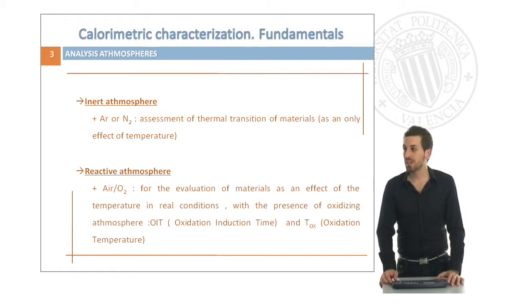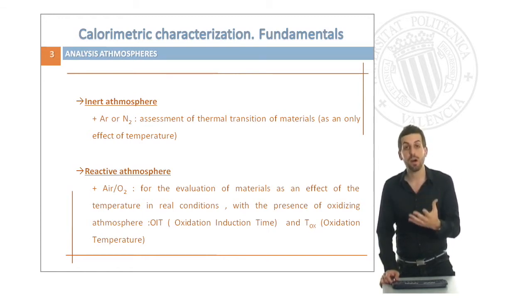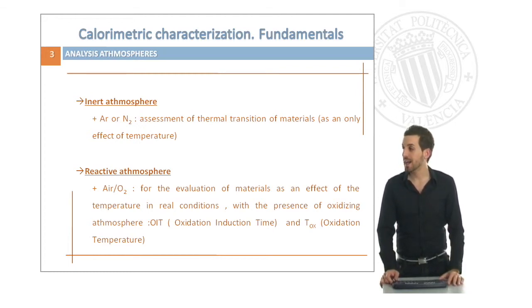Regarding the analysis atmospheres, we can perform different experiments according to the gas that we are using. If we use an inert atmosphere with argon or nitrogen, we will be able to assess the thermal transitions of the materials only as an effect of the temperature. But if we want the evaluation of the thermal transitions in real conditions, in some oxidative atmosphere, we can use air or oxygen to apply different experiments such as the oxidation induction time or the oxidation temperature.